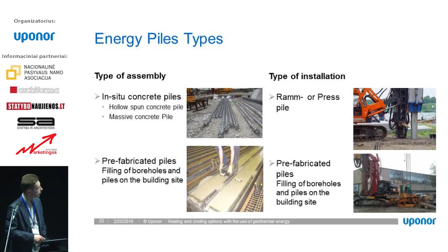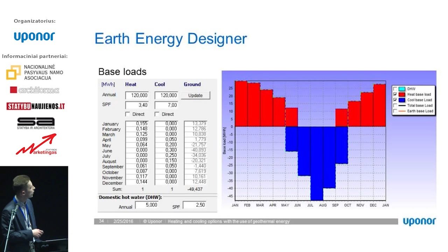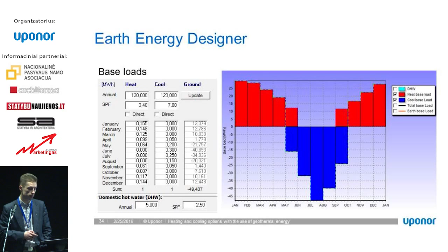For calculations, we can use special software such as Energy Designer, where we input the energy demand for heating and cooling. We need to know how much energy is needed for heating and cooling, ideally on a monthly basis - how many kilowatt hours for heating in December, January, February, and the same for cooling. Then we can make a diagram of the heating and cooling loads.